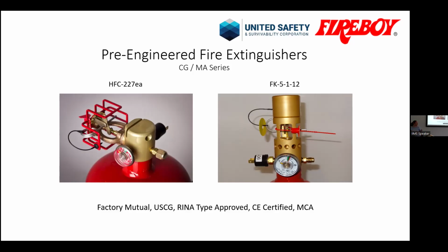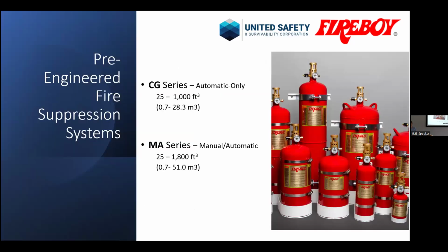Each of them will have a low pressure switch, which is the black switch with the two spades coming out of it. It's just a circuit that monitors a closed circuit. Basically, it allows you to monitor the gauge. So if you have a visual and audible indication at the helm, it will indicate low pressure, either during a leak, a fault, or in a discharge.